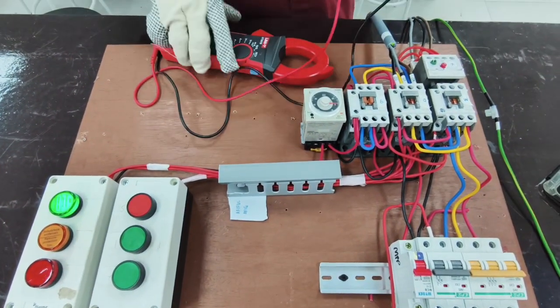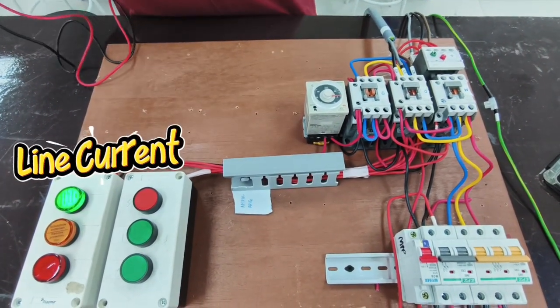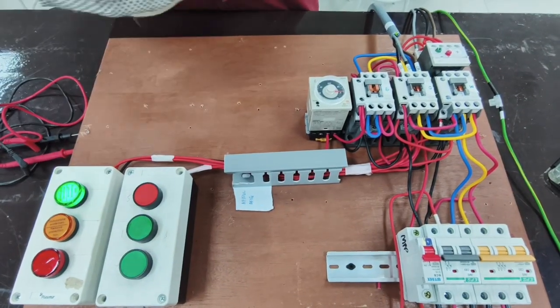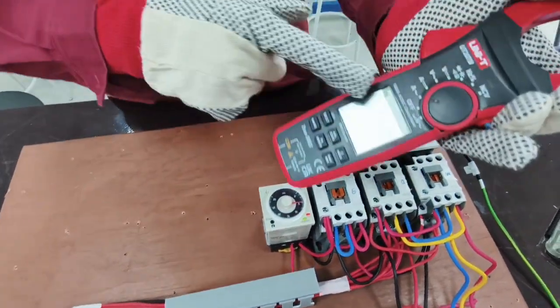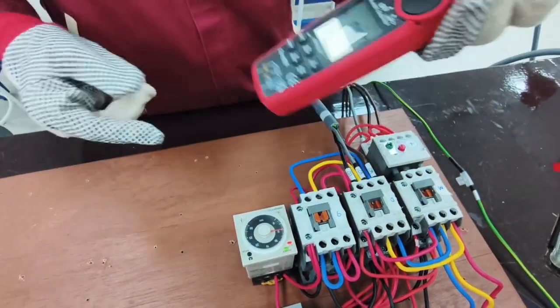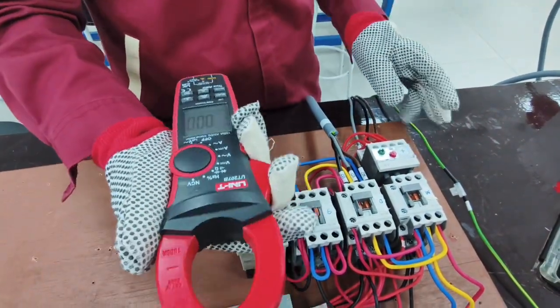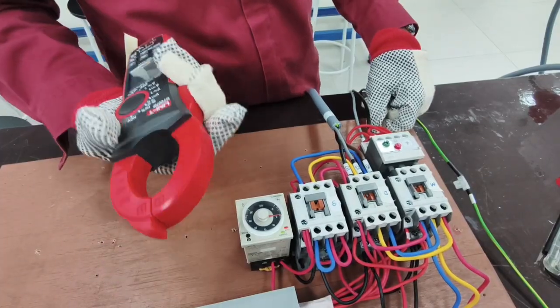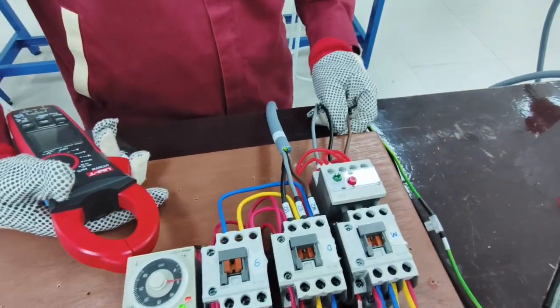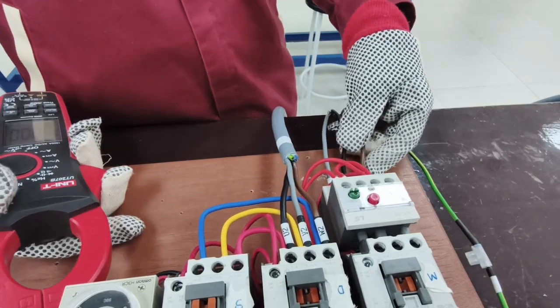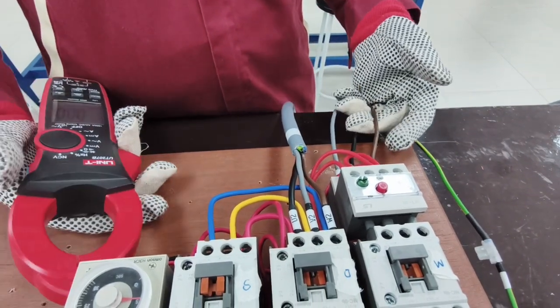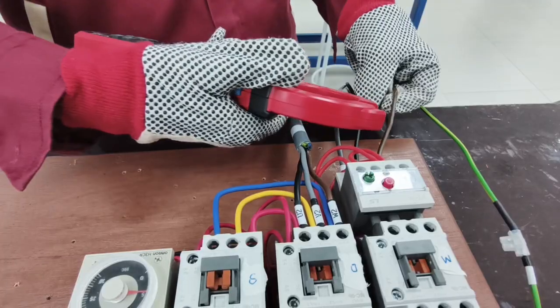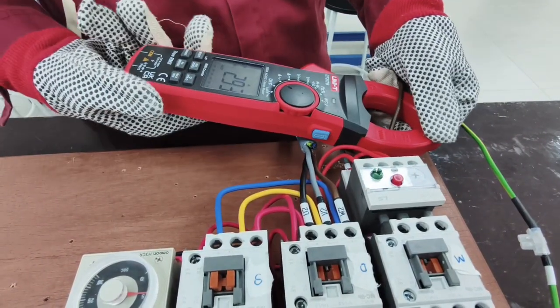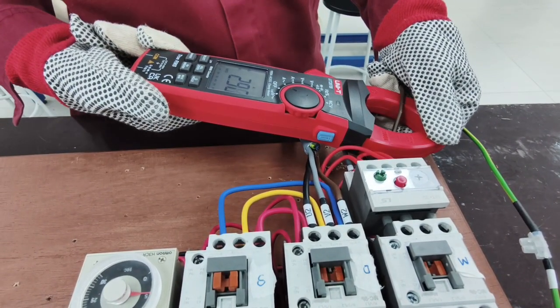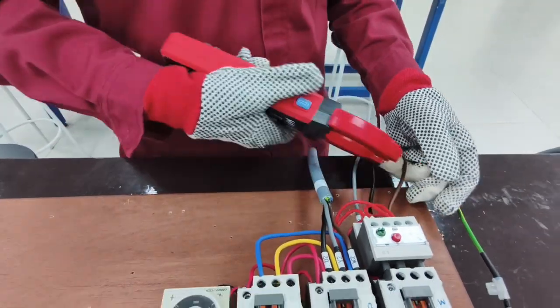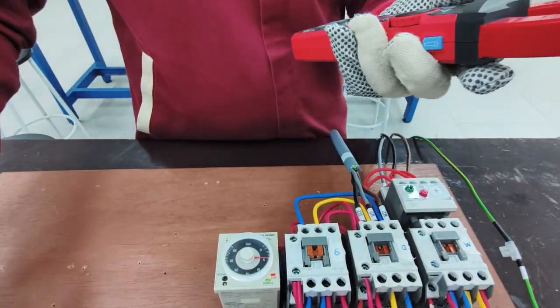Then we also can take the current reading from our working circuit. To take the current reading, we need to set to the current and AC. This is a clamp meter, so we just need to clamp the wire that we want to check the current flowing. If we want to take the current from red, which is U1, we just clamp it here and we can see the reading, 2.92 ampere.